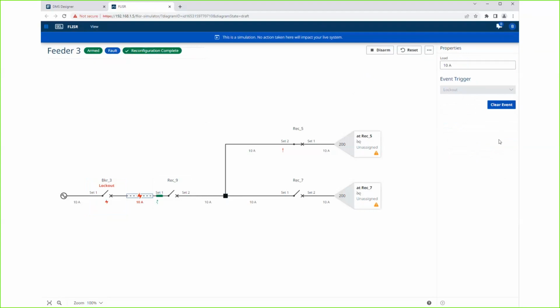And you can see that recloser 9 open, recloser 5 closed. So we used that @rec5 connection to an adjacent feeder to restore. The simulator assumes if you're putting a connection there that there's a feeder on the other side of it, and it will simulate that for you. So now we're issuing a return to normal, and it returns the circuit to normal.